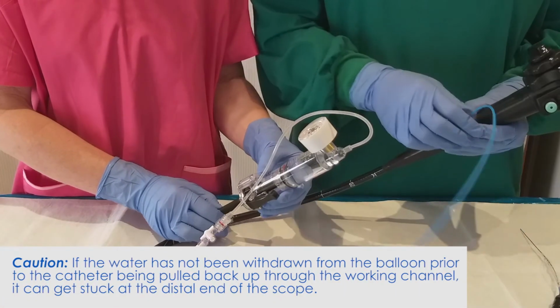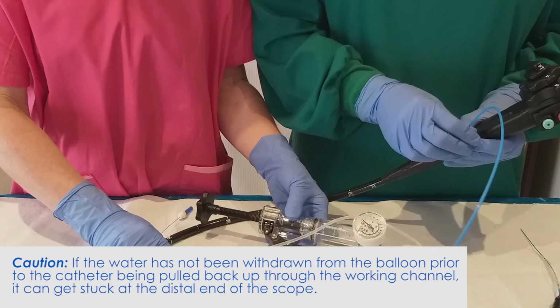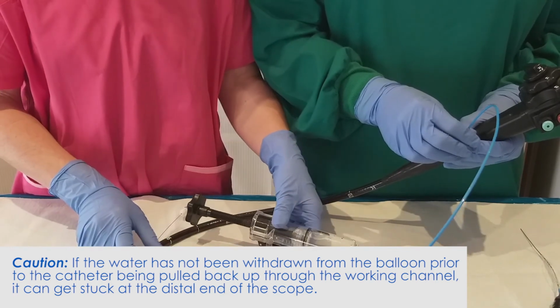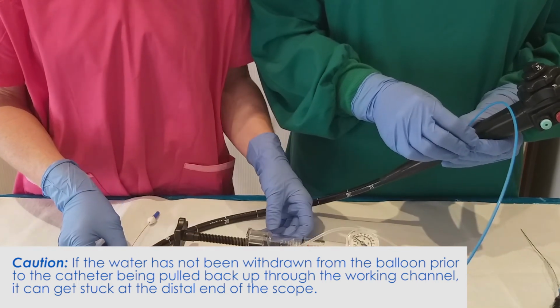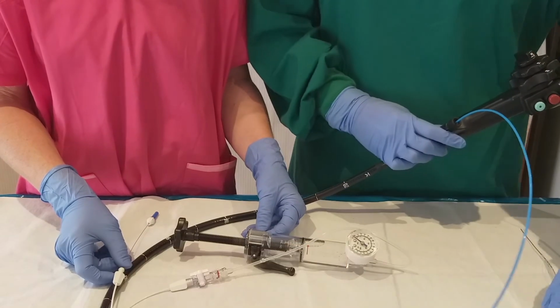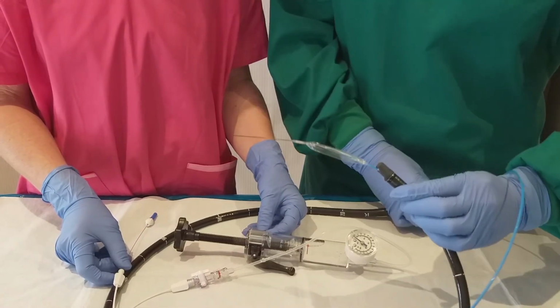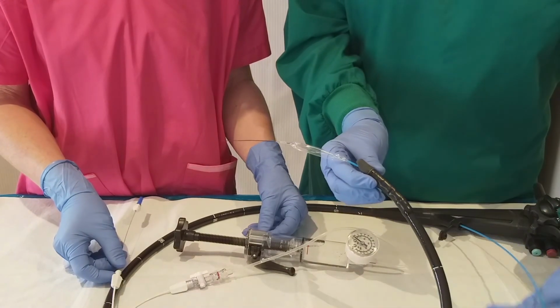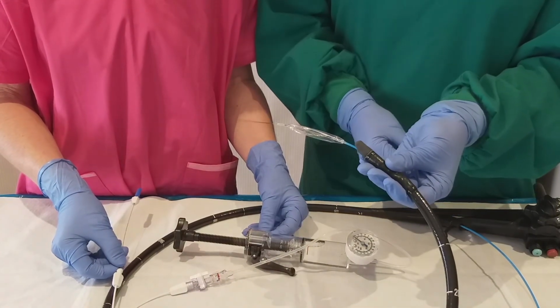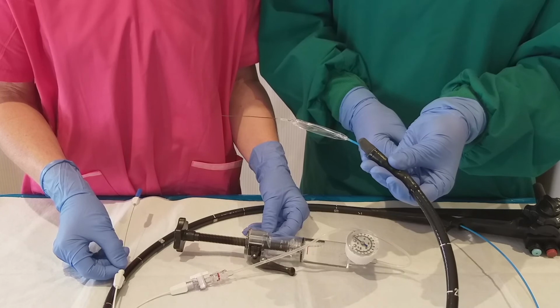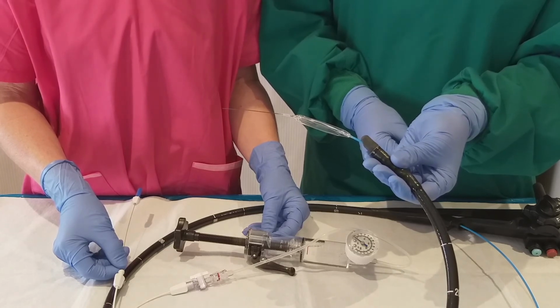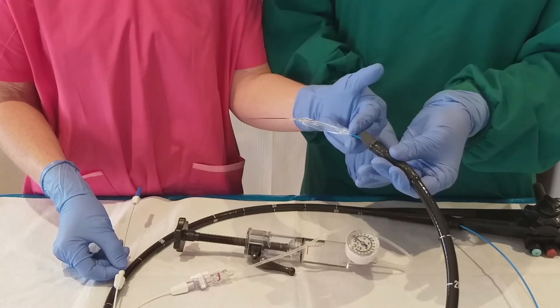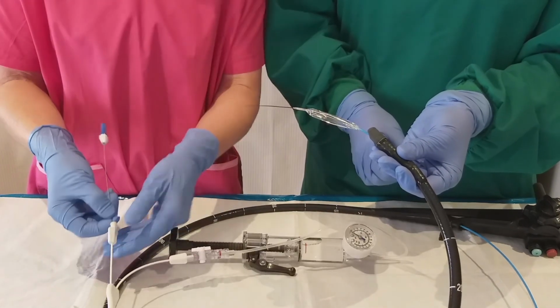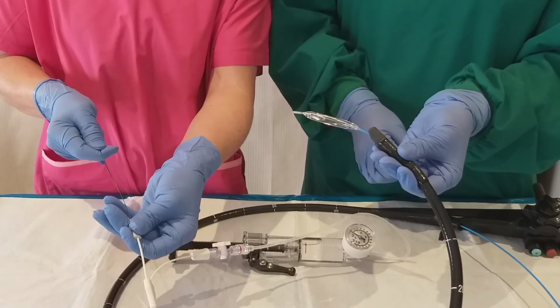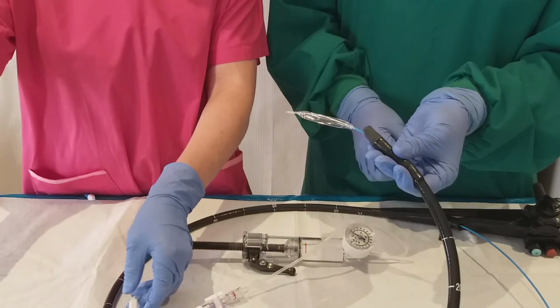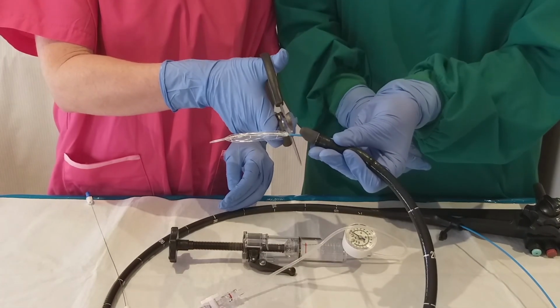Caution: if the water has not been withdrawn from the balloon prior to the catheter being pulled back up through the working channel, it can get stuck at the distal end of the scope. If this is the case, remove the endoscope with the balloon catheter inside. You will then need to extend the catheter out of the distal end of the scope and cut the sheath at the join of the balloon and sheath. If you do not have wire cutters, pull the guide wire back so that it is not evident in the balloon, and then you can cut the sheath with scissors.